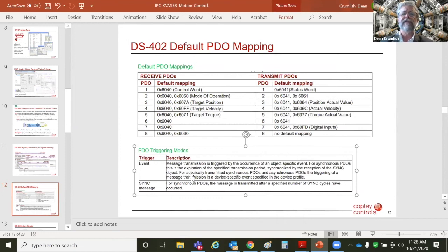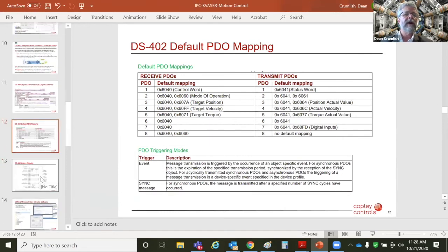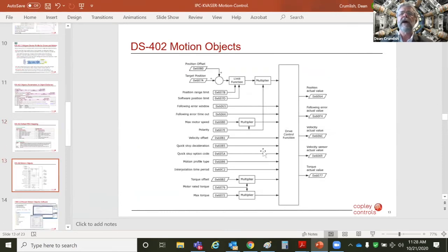Many things can trigger a PDO to transmit. You can wait for the sync message, say after every 100 milliseconds or 10 milliseconds, whatever you set it to, so you don't flood the network. And then an event, like the input changes. Let me know when the input changes, or let me know when the status changes. So events can trigger messages being sent on the network.